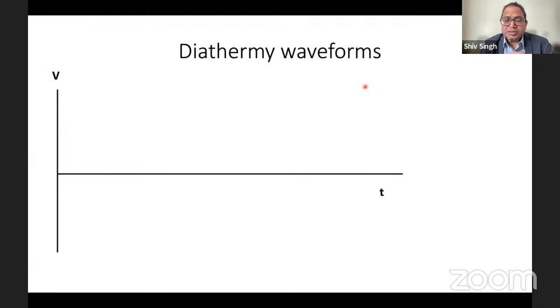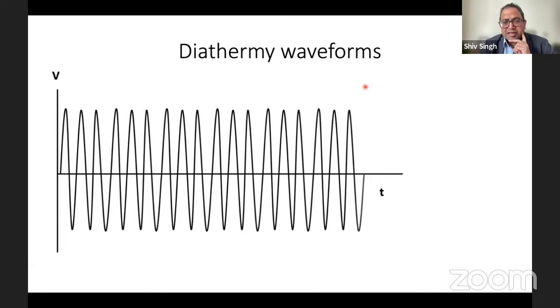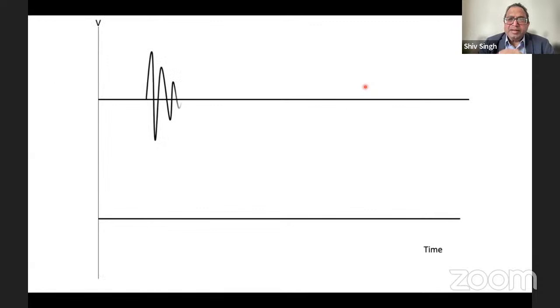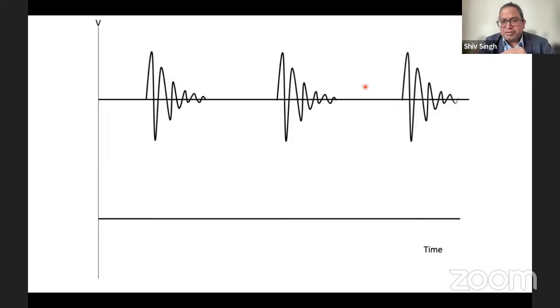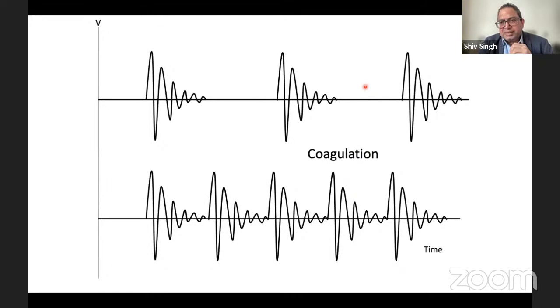So coming to the diathermy waveform, this is a continuous sine waveform, and this is used for cutting. When you have an intermittent damped sine waveform, this is used for coagulation. But if you combine the two, so you have the damped sine waveform, but it's continuous, not intermittent, this is called blend. So it can do cutting and coagulation together. This is used in urology and it's called a blend. So these are the different waveforms. Sometimes the examiner will give you a card with these and ask you to identify them.